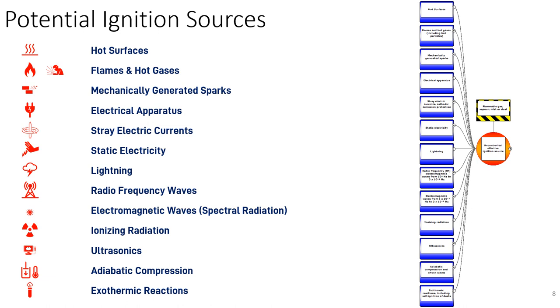We have a very useful list of potential ignition sources from BS EN 1127 part one. This document on explosive atmospheres, explosion prevention and protection gives 13 different possible ignition sources — ranging from the obvious hot surfaces, flames, and hot gases down to adiabatic compression and exothermic reactions. These may be less common, but they are still competent ignition sources with the potential to cause fires and explosions.